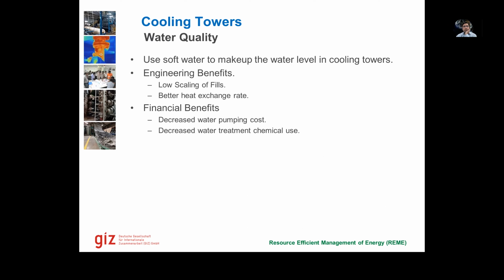Water quality is also important. It matters whether we are using soft water to make up water levels, or what kind of water we are using. If we use soft water, then we have low scaling of fills and better heat exchange is achieved. Obviously, the water pumping cost decreases in this case, and the water treatment cost would also decrease if we have better systems.